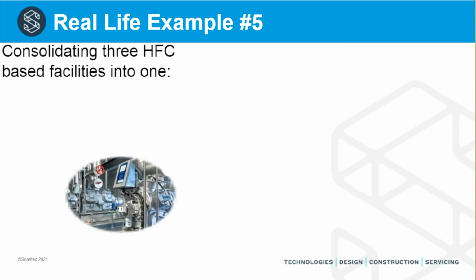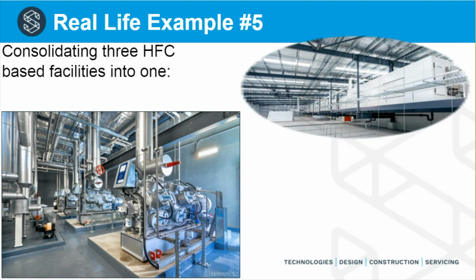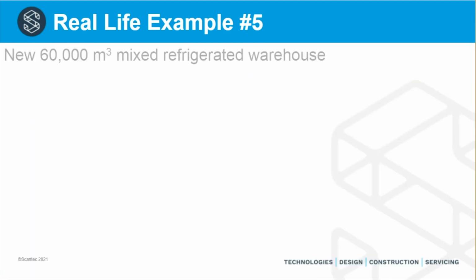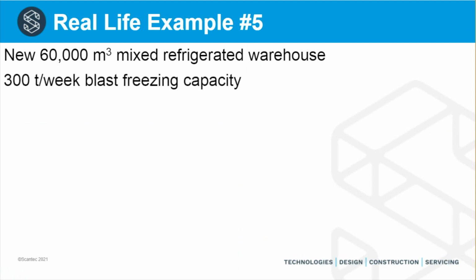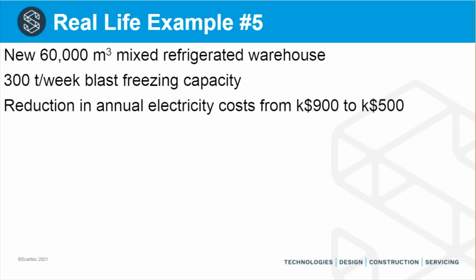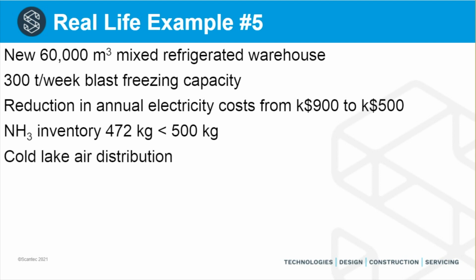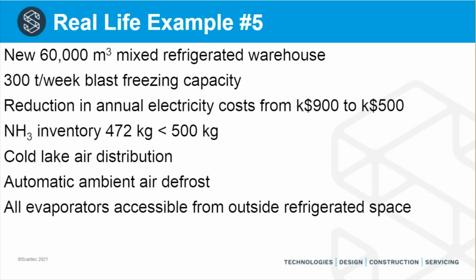And the final real-life example is a chap who consolidated 3 Freon-based facilities into one and reduced his electricity bill from very close to $1 million to $500,000 a year, while at the same time having a significant increase in refrigerated volume. The ammonia inventory is 472 kilos for 60,000 cubic meters of refrigerated volume. The 500 kilos is a threshold in Australia. If the facility has more than 500 kilos of ammonia inventory, it is classified as a dangerous goods storage facility, which means it is subject to additional compliance requirements that cost additional money.